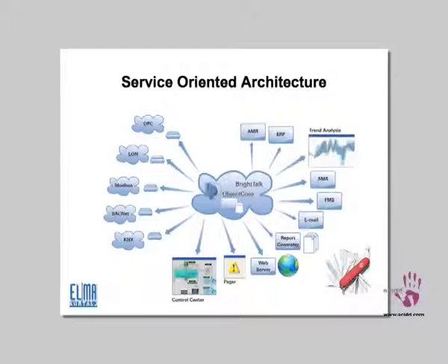So you have these languages of the building on the left side, like OPC, LON, Modbus, BACnet, KNX. Those buzzwords you will hear more and more in the future. And then there is a bright node, these blue boxes, which are actually part of these networks. So they talk the language natively, very natively. They transform it to the universal object infrastructure, and this ObjectCore is basically the information broker, which translates that information so the average ICT person can use it.